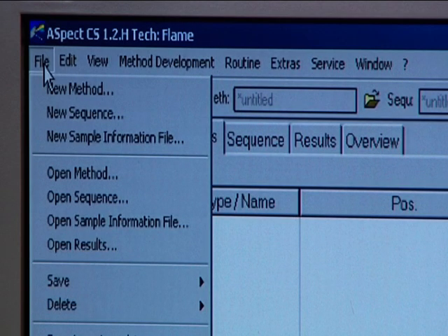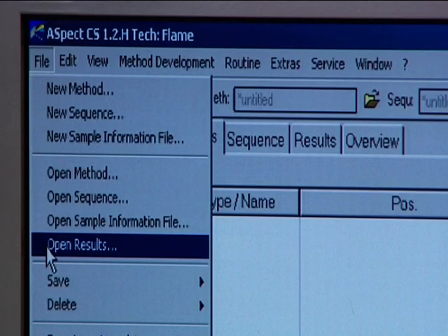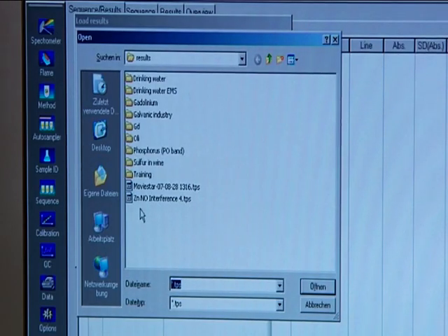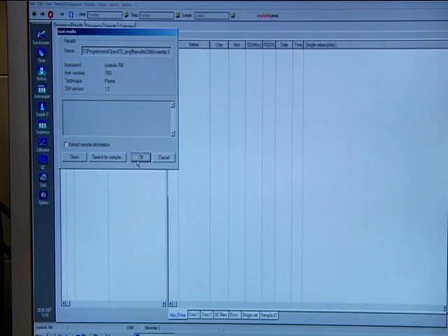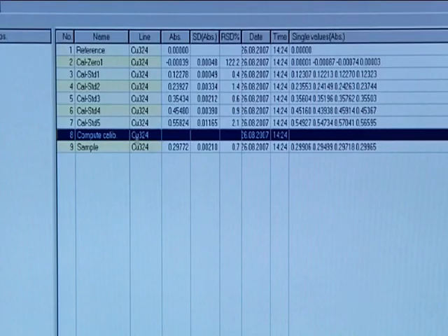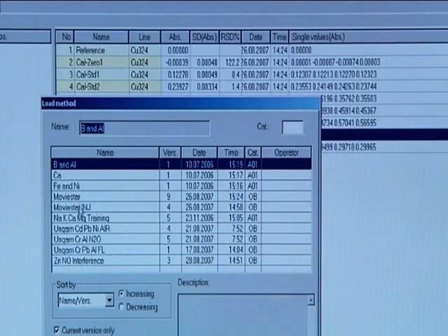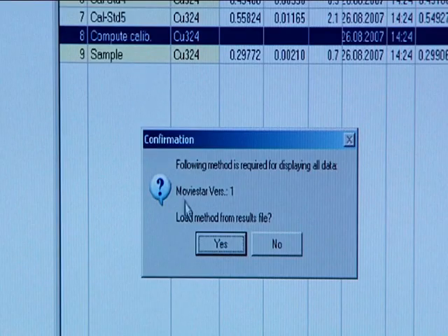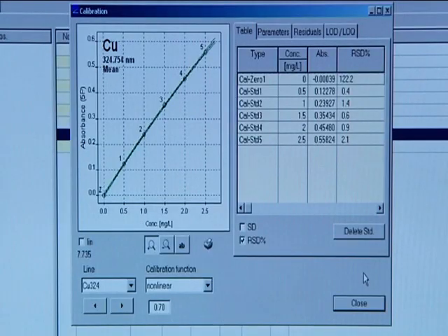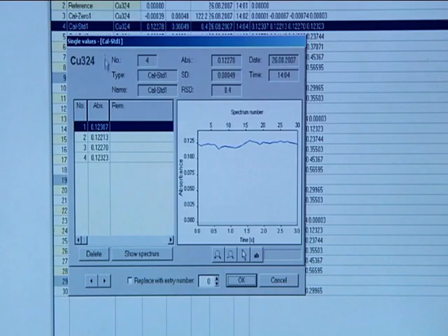Additional spectrometer functions, such as handling and processing spectra and correction models, can be handled more easily than ever. Each sample spectrum is indicated during a measurement. Measurement errors are recognized immediately and malfunctions can be identified quickly. Each result file contains the complete package of information of how the measured value came about, from the parameters over the raw data to the results of the analysis.